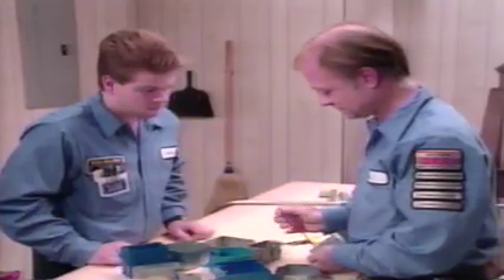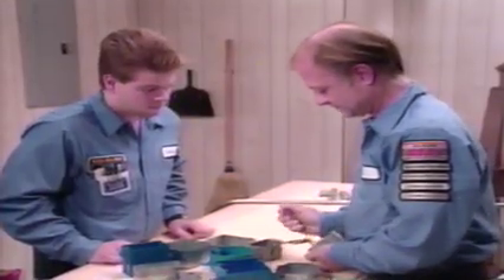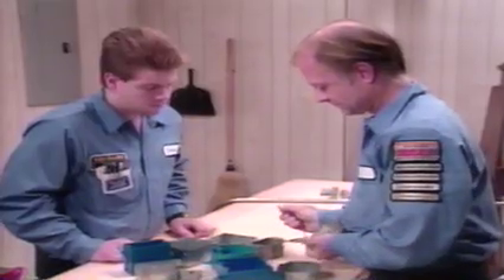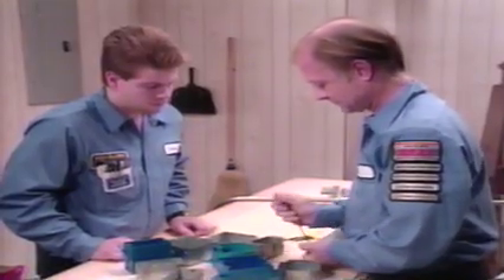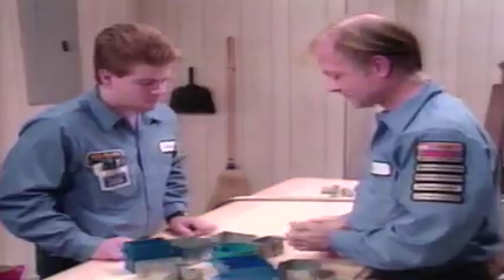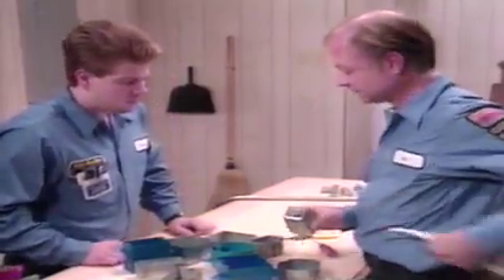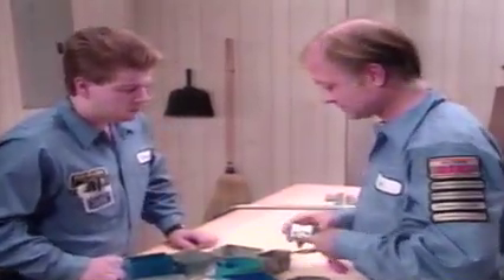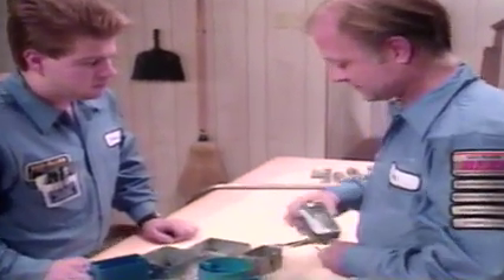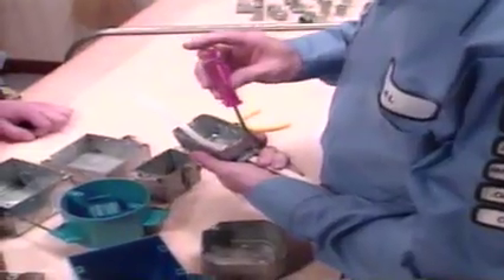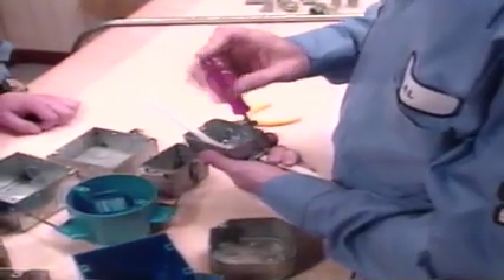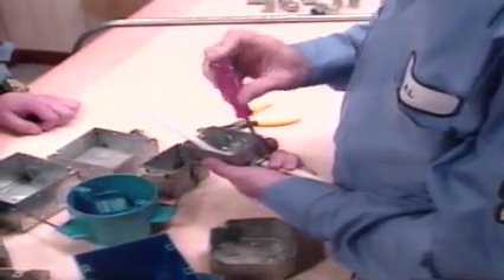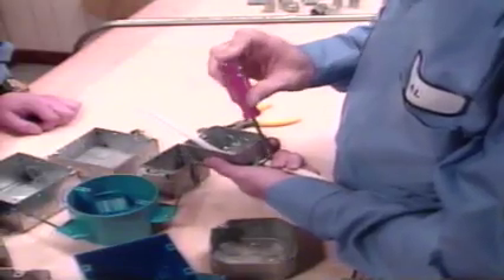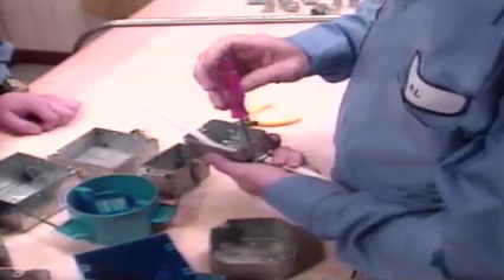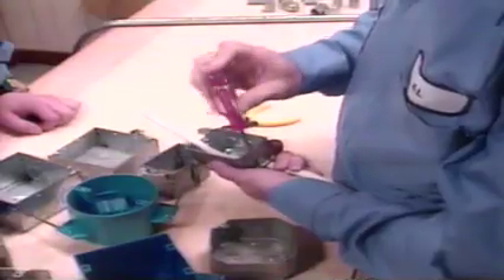To secure the wire going into the box, use a Romex connector. Put the connector into the box and tighten the lock nut to the inside of the box. Feed the cable through the connector, making sure that you have enough cable, approximately 8 inches, to make your connection. Tighten down the 2 clamp screws. Give the cable a tug to make sure it is securely clamped. Then strip the cable sheathing back to where it enters the box.